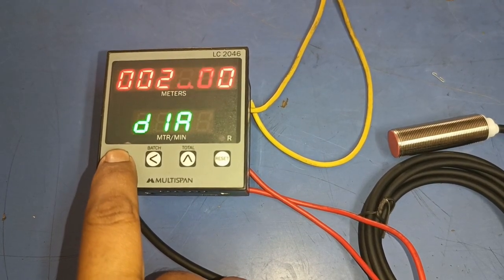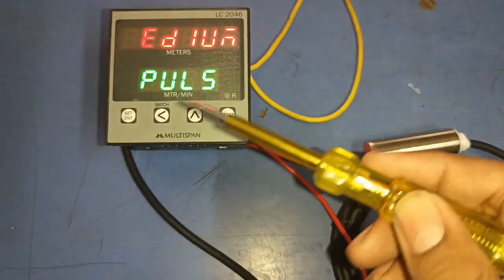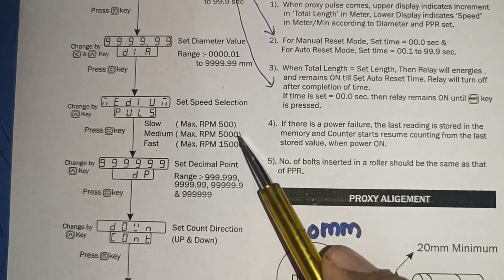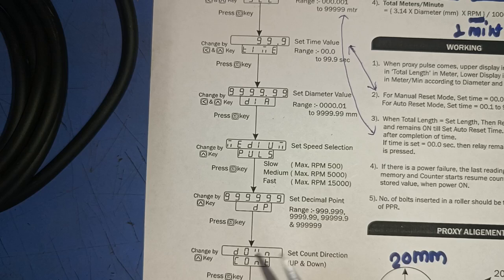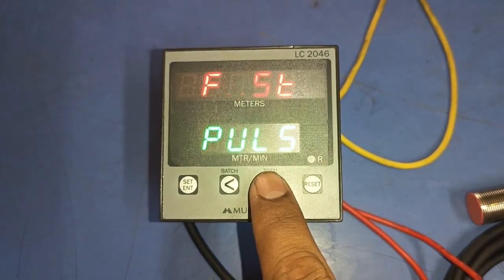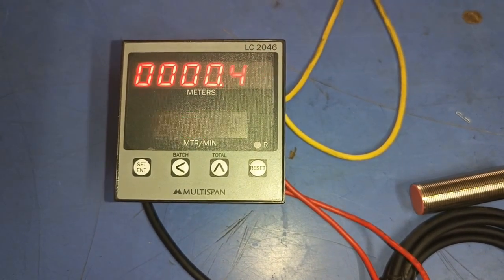The next parameter is for pulse sensing speed. If your sensor senses up to 500 times per minute, set it to Slow. If sensing speed is up to 5000 times per minute, set it to Medium. If sensing speed is very high, set it to Fast. Since our machine speed is very slow, we set Slow for the sensor sensing pulse parameter.